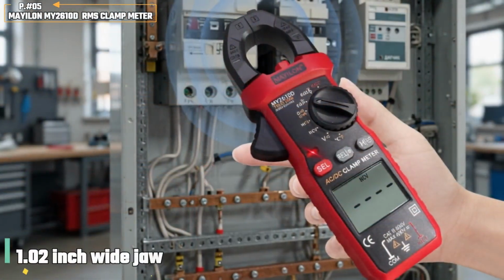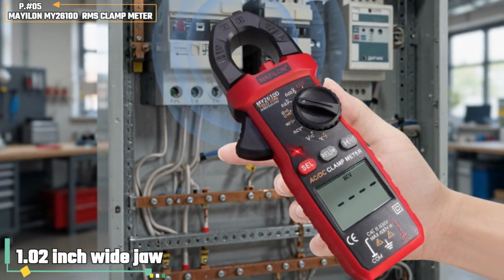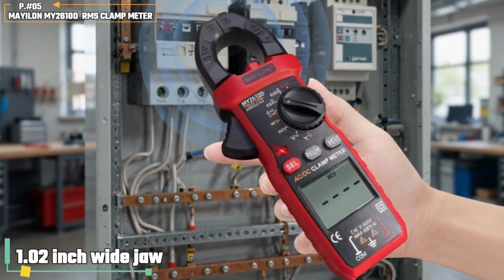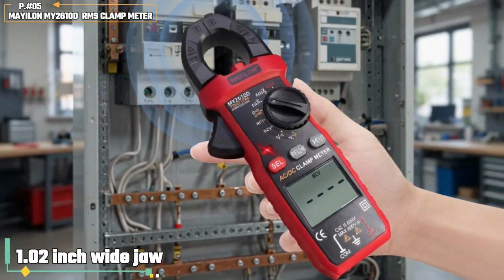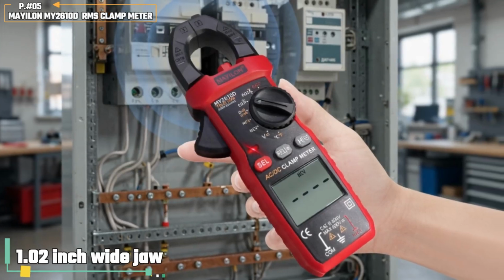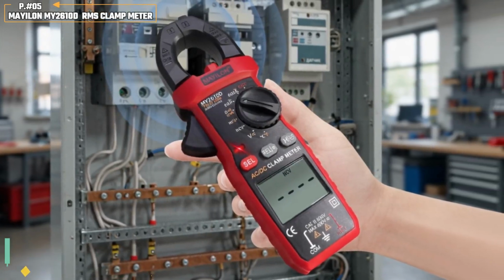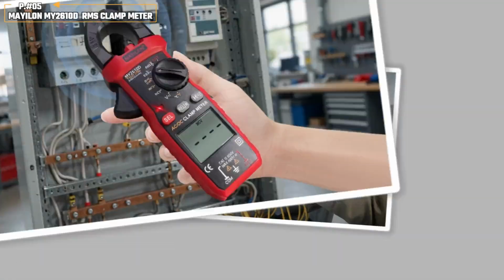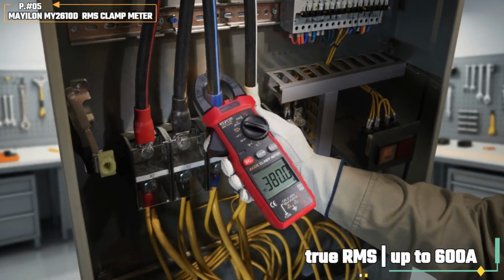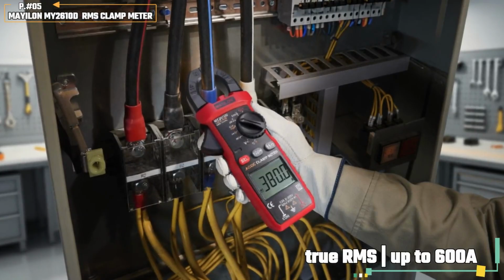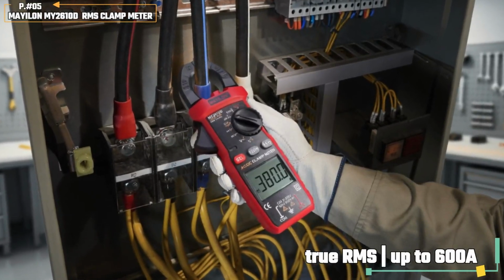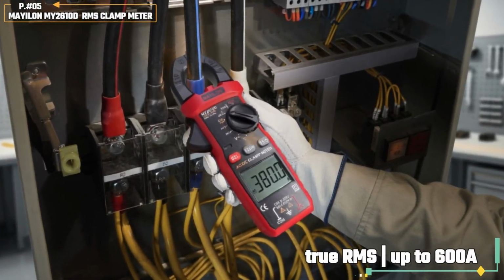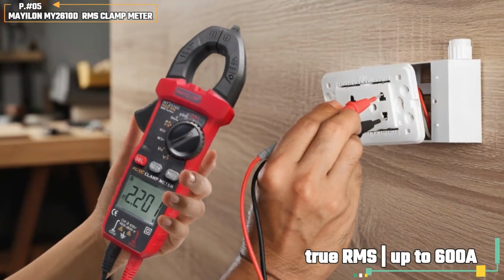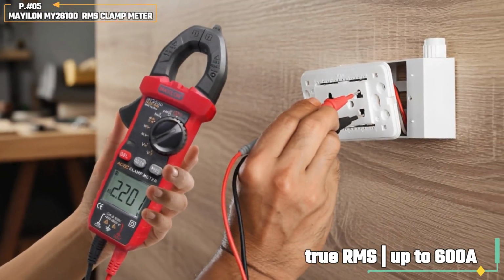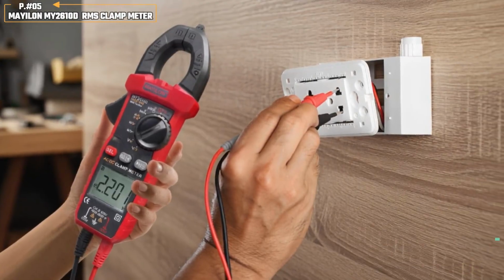The 1.02-inch jaw fits around individual conductors and automotive cables without disconnecting the circuit. Its backlit display and built-in flashlight also make testing easier inside dark panels and tight spaces. The 6,000-count True RMS system provides more dependable AC readings on electronically controlled appliances and other distorted electrical loads. It can measure AC and DC current through the clamp, with ranges reaching up to 600 amps.